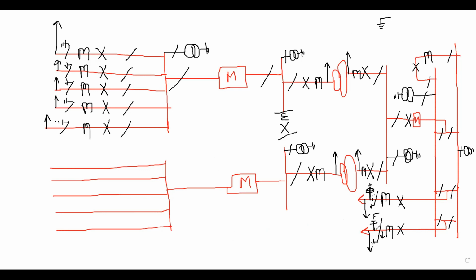Fine. For auxiliary consumption, for breaker closing or opening, isolator closing or opening, transformer switching, fans, and the whole system illumination, you require some auxiliary supply. 33 kV is the supply here, and 220 kV is one more supply. So how can we get the 415 volt supply, which is the voltage required for lights, fans, and motors? You need one more transformer, stepping down the 33 kV voltage to 415 volts, connected this way.